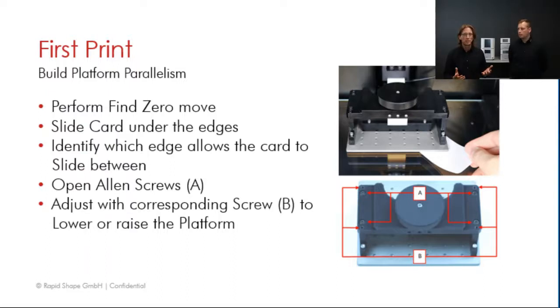Which basically means after you did the adjustment, you fix the position with screw A, you make a move upwards or a reference move, followed by another find zero move. And this way you can cross-check if your adjustment was done the correct way, if the machine is prepared.